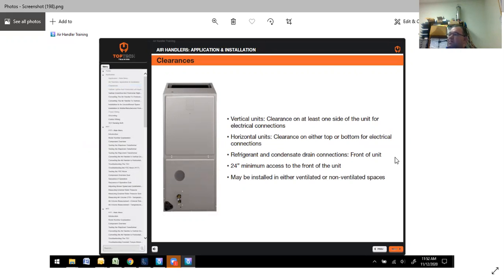Vertical units need clearance on at least one side of the unit for electrical connections. Horizontal units need clearance on either top or bottom for electrical connections. The big one is refrigerant and condensate drain connections. They give you plenty of connections to use, depending on your application orientation, but you have to make sure that the drain is installed properly, you have access, you install a trap, and you don't block the filter.